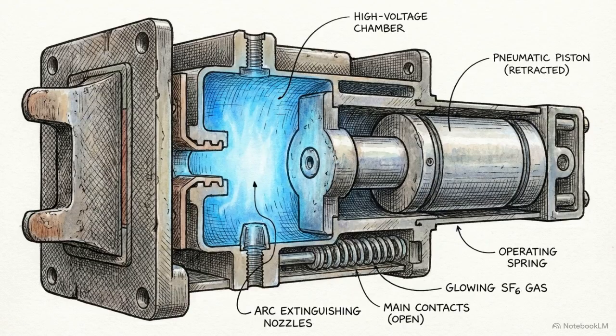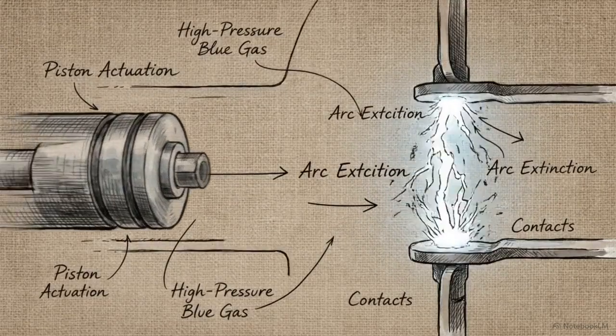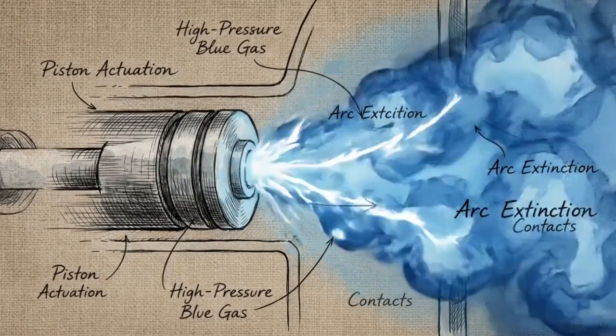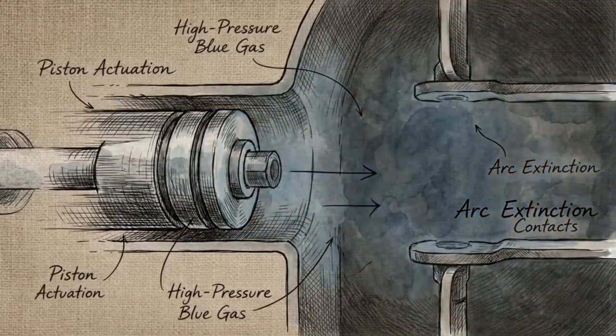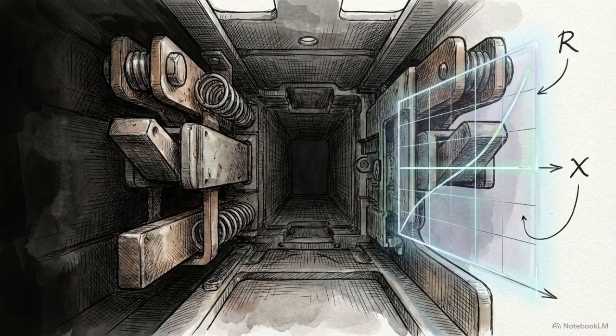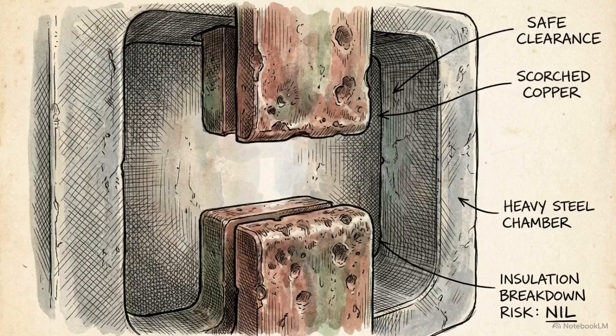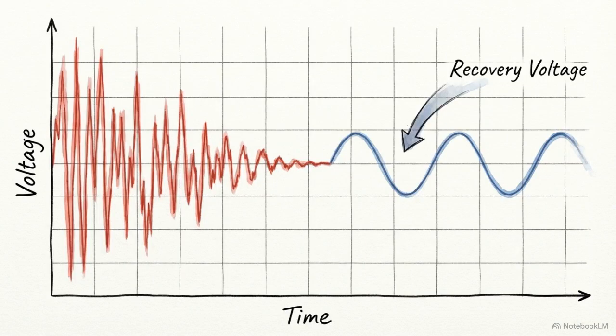Because they know the exact speed of that spike, the breaker can fight back. Before the voltage can rebuild, the breaker fires a high-pressure blast of special insulating gas, or a vacuum, right into the gap, suffocating the arc before it destroys the hardware. Physically breaking the circuit is a calculated race against the violent physics of restriking voltage. Once that gas clears the gap and the arc is successfully extinguished, the connection is completely severed. Returning to our graph, the chaotic high-frequency spike fades away. What takes over is a normal, stable rhythm called recovery voltage. The fault is gone and the system is stable.